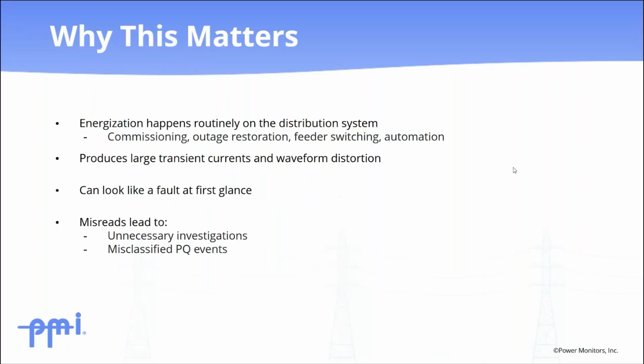Why this matters. Transformer energization happens all the time on the distribution system. You'll see it during equipment commissioning, restoration after an outage, feeder switching operations, normal distribution automation activity. And the catch is that when a transformer energizes, it can produce large transient currents and significant waveform distortion. At first glance, that activity can look like a fault, which means without proper interpretation, an energization event can trigger an unnecessary investigation or get misclassified in a PQ monitoring system entirely.